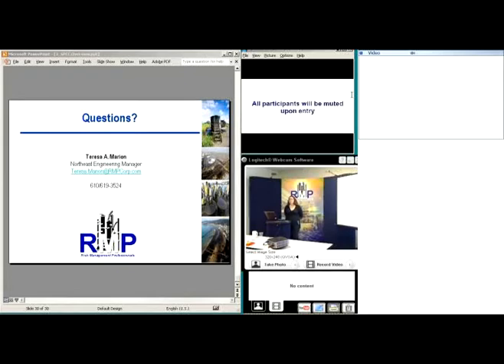Next question. Are there annual reporting requirements for Tier 1 facilities like there are for Tier 2 facilities? With the SPCC, there are inspection requirements. In general, the plan is required to be reviewed every 5 years. Obviously, if you make a major change at your facility, adding or reducing capacity, you'll want to go through at that time and update the plan. In the checklist, it will guide you on the specific inspection requirements, and I think that's what you're getting at. Specific inspection requirements are going to have different time frames. They may have a six-month period where they want you to look at your containment, check it out, walk around. They may have some monthly, and that will be right in the checklist and provide you guidance.